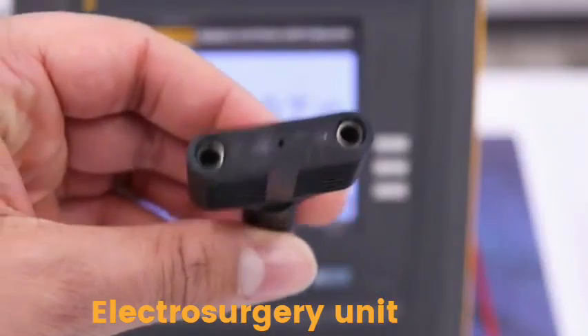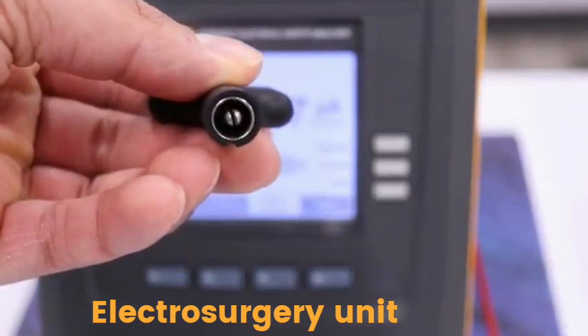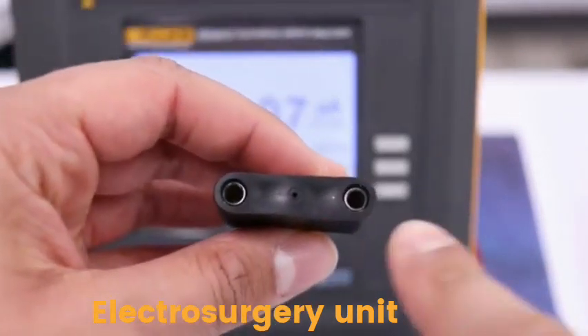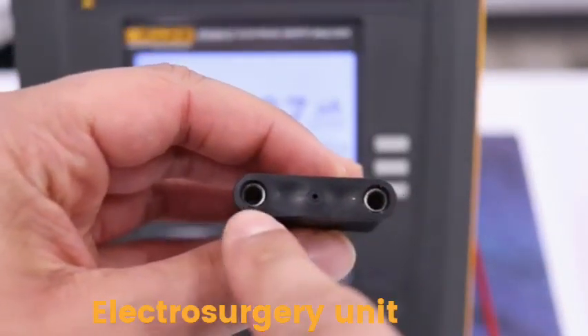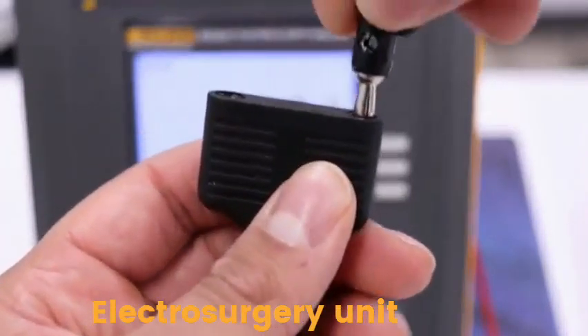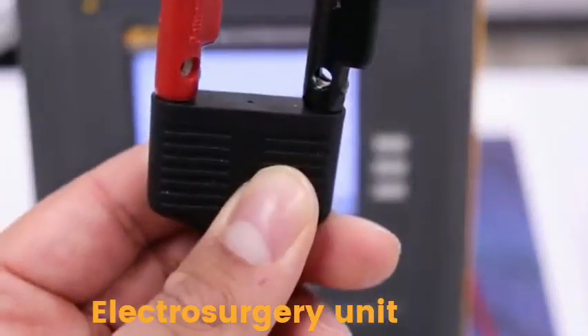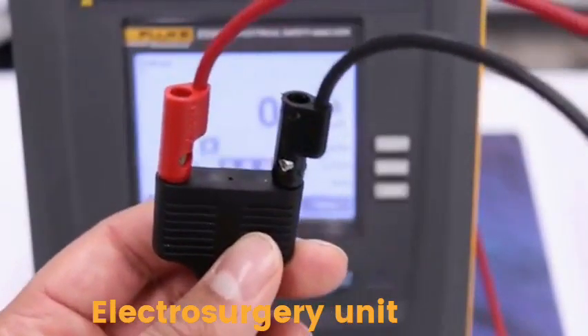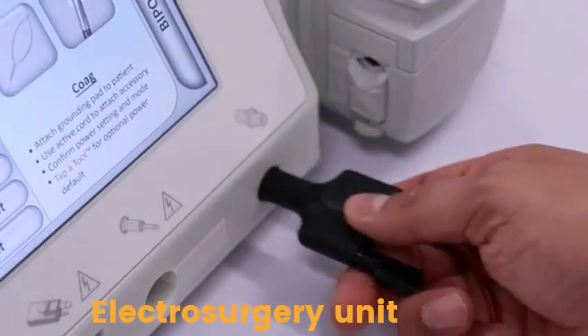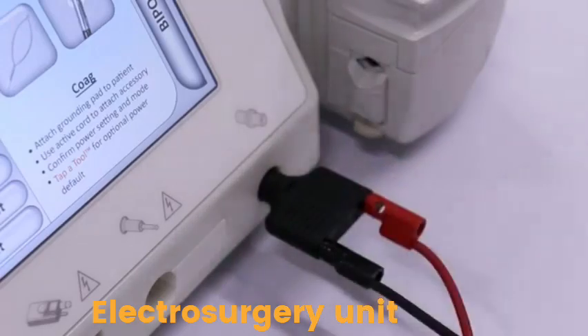The bipolar test adapter divides the active and dispersive lines within the bipolar circuit. Plug each end of two separate 4mm test leads into the bipolar test adapter. Plug the bipolar test adapter into the bipolar receptacle on the GI4000.